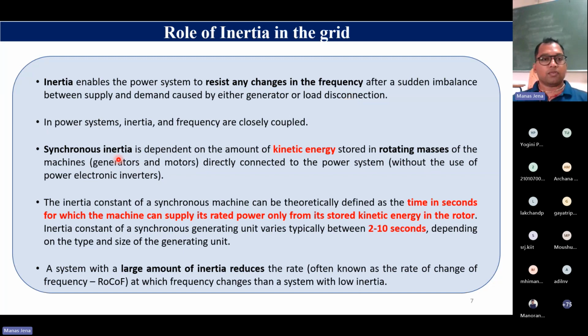And luckily we have the synchronous inertia, which essentially refers to the kinetic energy stored in the rotating masses of the conventional machines, which takes care of this inertial response, isn't it? In our power system control theory we have studied that after the contingency, the first thing which comes into the picture is the inertial response. From where does it come? This is what helps us, right? And it is there by default, inherently part of the machine, which helps in arresting the frequency deviation.